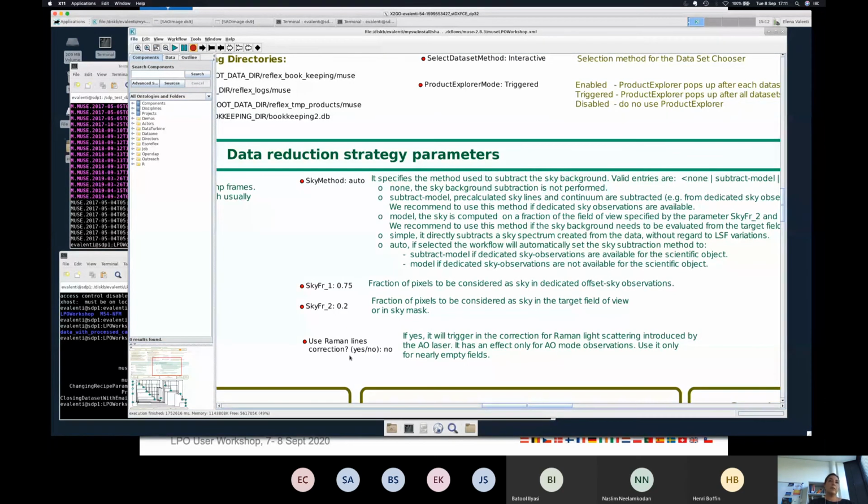And this is because this Raman line appears because of the back scattering of the sodium laser, and you can look in the user manual to check what is the exact wavelength at which these Raman lines appear, but in general, very close to the region where the notch filter is. The notch filter is the filter that blocks the emission line due to the laser.